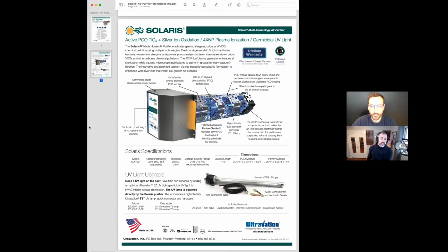And I love that kit too you're sharing there, because it's hard to see for some people, but there's actually directional shielding clipped onto the lamp. So it actually ensures even more of that light emanating from the 360-degree exposure of the lamp. That reflective surface will then push all of that down onto the coil once this is installed. So we're getting as much UV as possible off of a single lamp install over top of a coil.